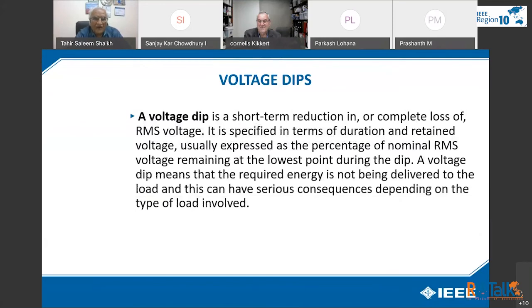A voltage dip is a short-term reduction or complete loss of RMS voltage. It is specified in terms of duration and retained voltage, usually expressed as a percentage of nominal RMS voltage remaining at the lowest point during the dip. A voltage dip means the required energy is not being delivered to the load, and this can have serious consequences depending on the type of load involved.